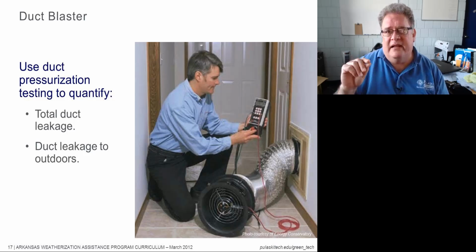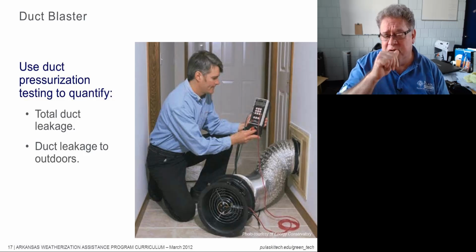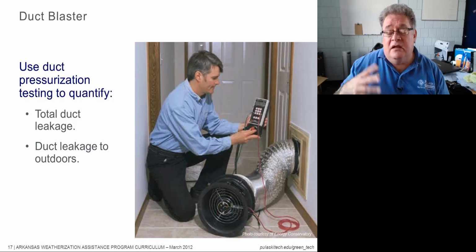However, if we have a bad air barrier, which would be a hole in the duct, and that hole goes to the outside, then we're going to see a pressure difference. However, duct blowers actually put air into the ducts, bring them up to a test pressure, and hold it there, and then determine how much air it's taking in addition to holding that pressure. What am I trying to say? In other words, it can quantify leakage for us. That is what it does. It actually quantifies.